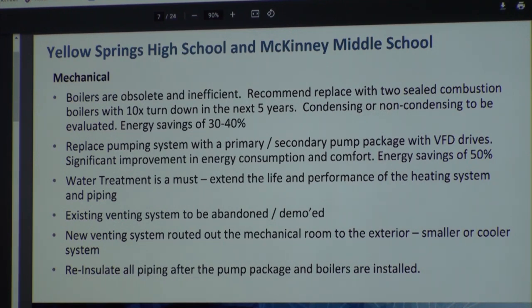So we've been kind of going back to some of the lower efficiency boilers that seem to work really well, and you're giving up maybe a few percent. With a condensing boiler on a really cold day, it's not working efficiently anyway - it's only working at 88 or 86% because it's running as hard as it can.